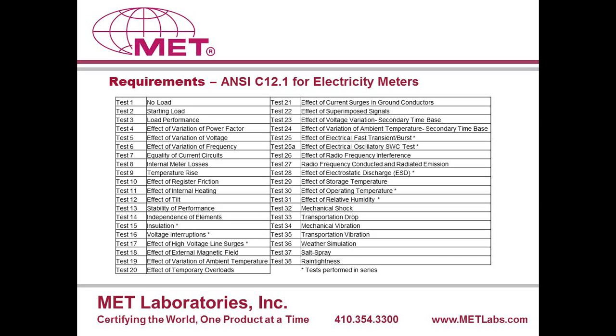One other thing to note about the 38 tests: you see 8 tests there denoted with an asterisk. Those 8 tests are considered series tests by the standard. There's some debate on whether or not you need to sequentially go through those 8 tests, starting at test 15, 16, 17. That's the way we handle it here at MET, mainly for consistency's sake. But the main point I want to make is that those series tests must be performed on the same 3 samples. So at the very least, the standard requires that 3 samples go through whatever test is applicable out of these 38 tests. So if you have one meter type, one type of configuration, then 3 samples would go through each of the applicable tests.